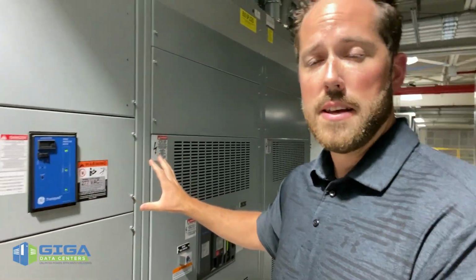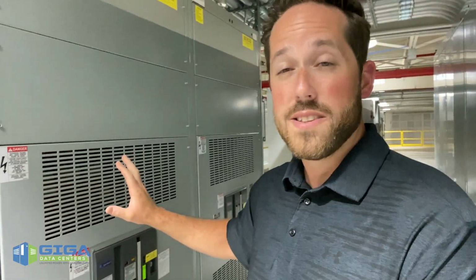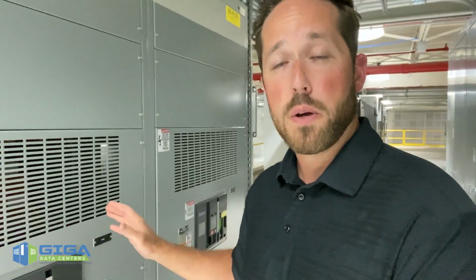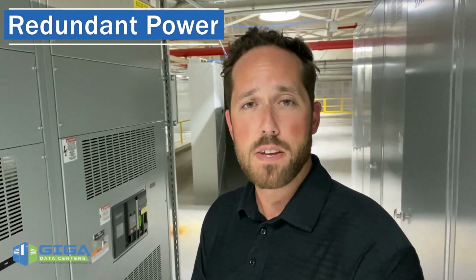From the bus duct below us, that power is being fed into our master switches. Our master switches take that power from the street and split it into dual feeds, so we can provide our customers with redundant power feeds into their enclosures, more specifically into the racks inside of their enclosures.